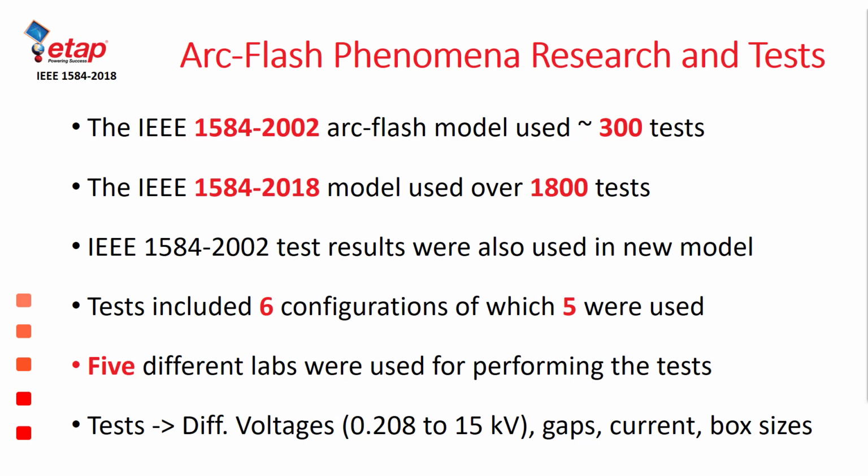The new testing was also done to be able to provide additional information which was missing from the previous 2002 models, and also as a response to several IEEE papers which showed that there were inconsistencies or gaps in terms of electrical configurations which could yield higher thermal incident energy results when present in the electrical equipment.